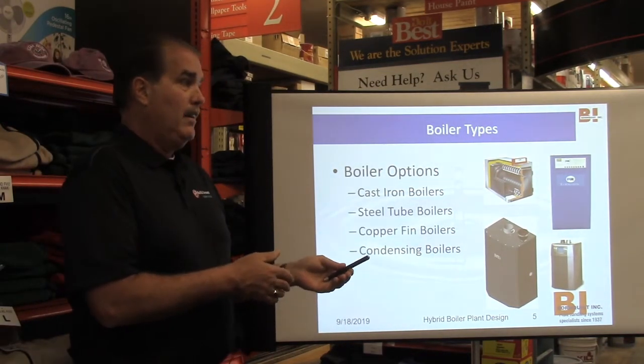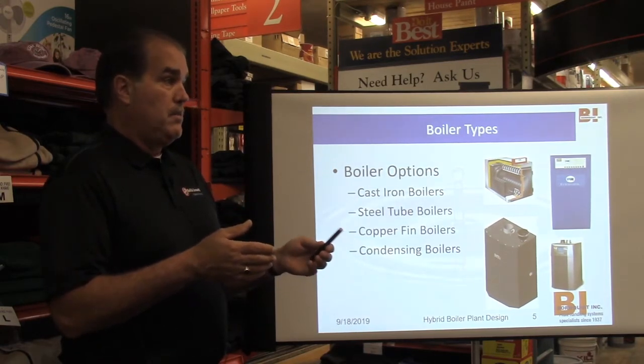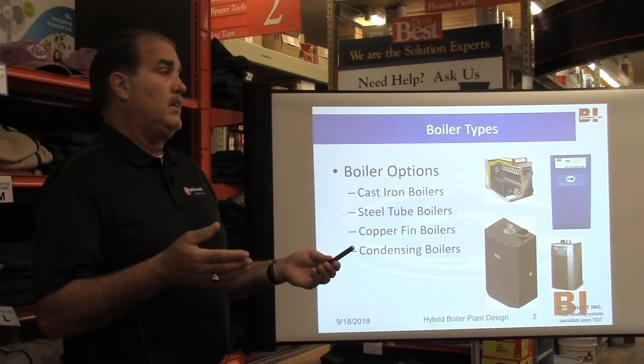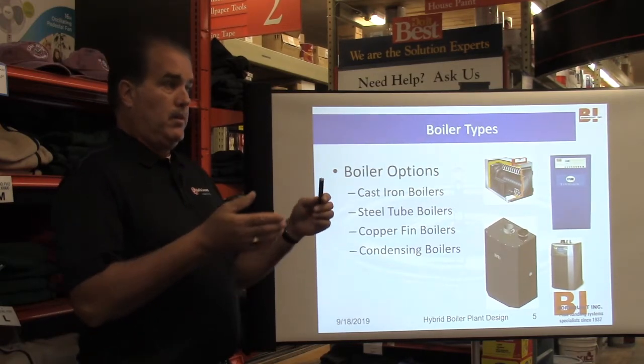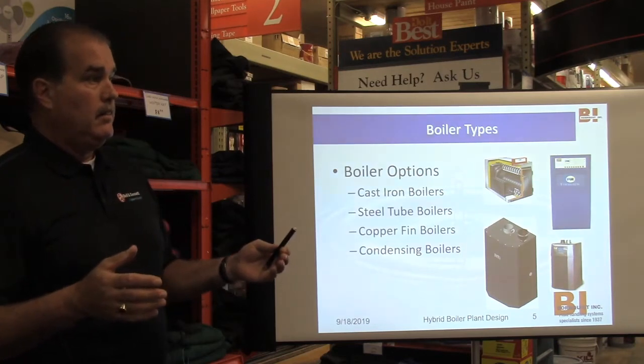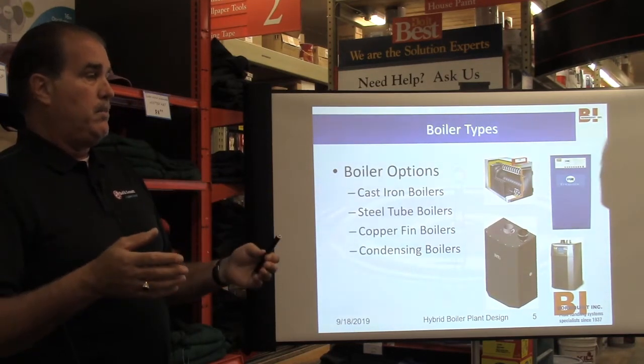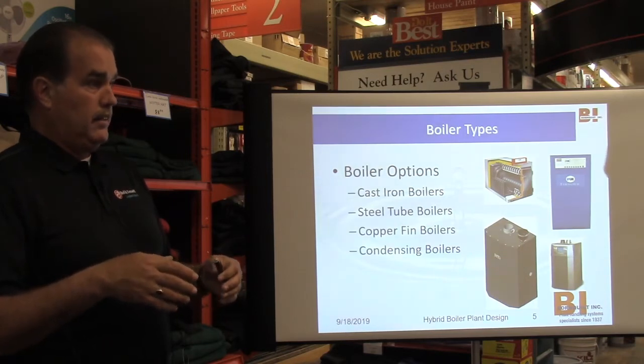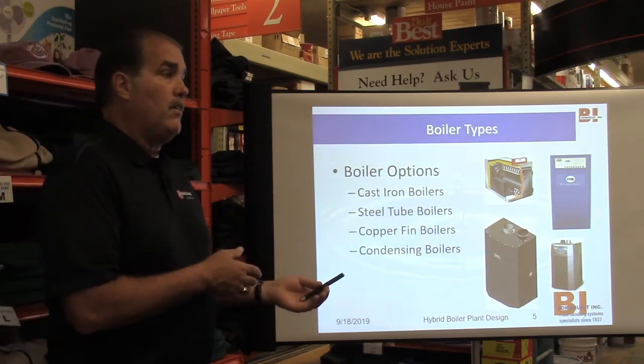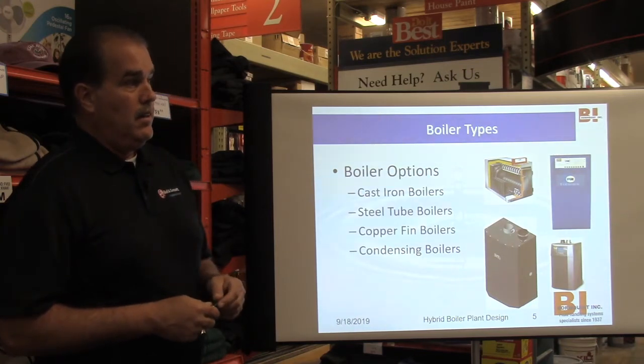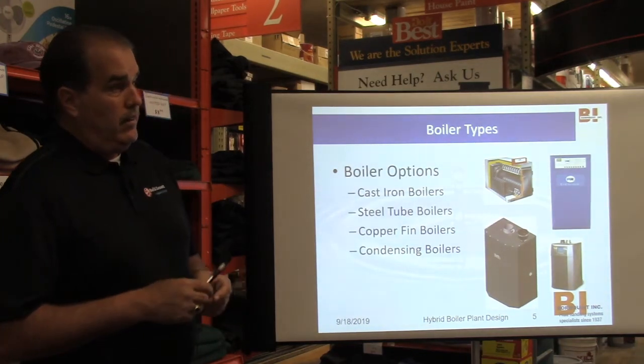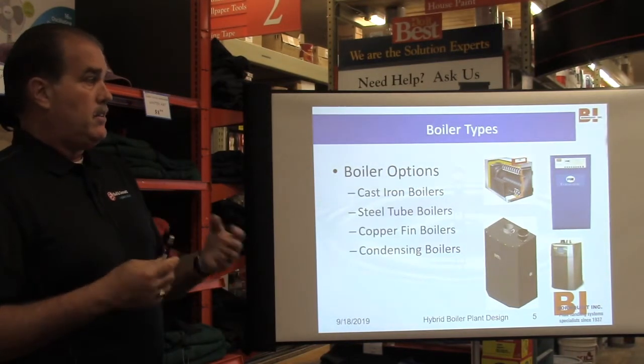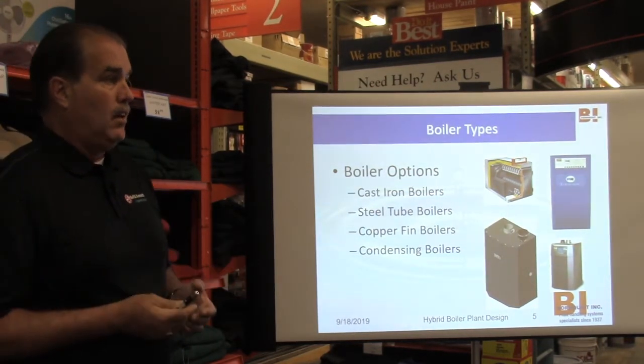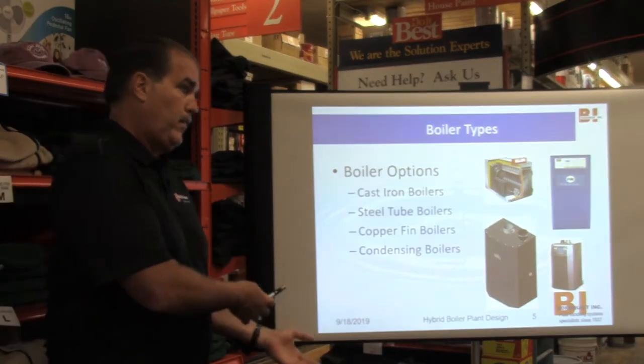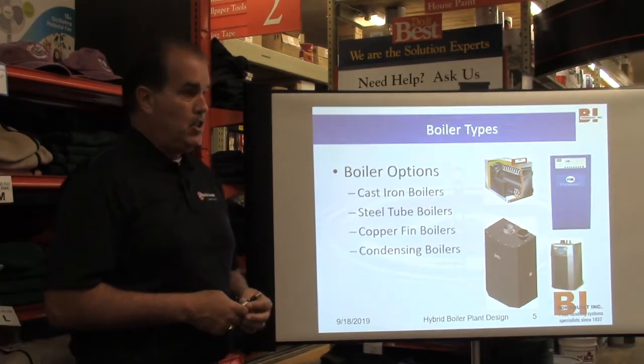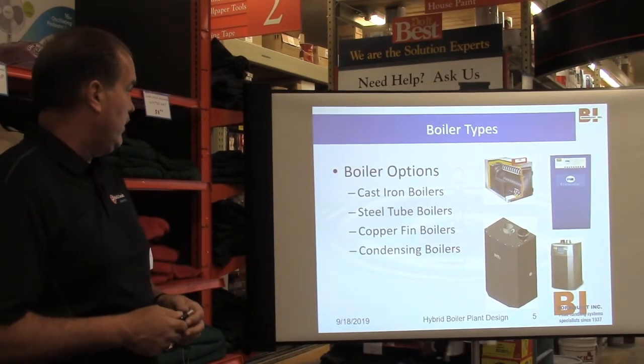They're not going to go smaller, which may be the wrong way to go, because you may not necessarily need all that. If you really think about it, today's buildings compared to buildings of 40 years ago are sealed up a lot tighter. They're a lot more efficient. The lighting's more efficient. Plus, you have a lot more heat emitters inside your building, like computers and stuff that wasn't there 30 or 40 years ago. No pilot lights. Light bulbs are cooler. So there's a lot of stuff that makes the building require less of a heat load, and the boiler downstairs probably hasn't been changed to accommodate that. But that's just, you know, that happens.